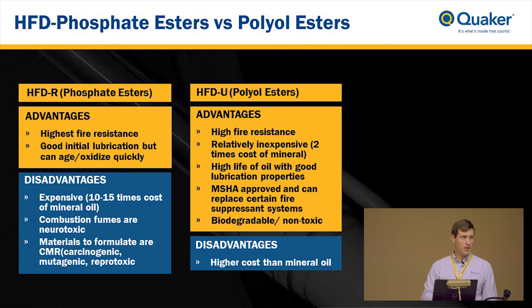So phosphate ester has a place but definitely has some disadvantages. The synthetic polyol ester is extremely fire resistant. It is relatively less expensive compared to a phosphate ester — about twice the price of mineral oil, and that's really the only con. It has the same anti-wear and mechanical properties as mineral oil so you can plug it in directly. In this area MSHA also certifies it for use underground, so you can replace certain fire suppression systems underground rather than adding a new system. It is also biodegradable and non-toxic, making it ideal for environmentally sensitive areas.